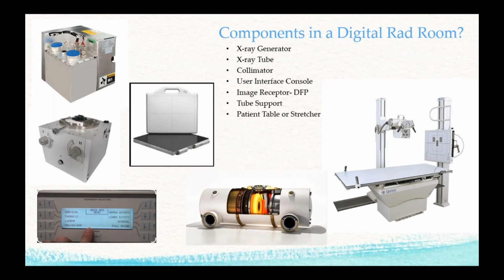So mounted to the X-ray tube right over here, we have something called a beam limiting device, or a collimator. It has lead blades inside of it, and we can control the size of the X-ray beam coming out of the X-ray tube. X-rays come out of a tube in a cone fashion. If you picture an upside down ice cream cone, that's how it's leaving the X-ray tube. So it's divergent as it goes out. It not only spreads wider, but gets weaker the distance that you give it, right?